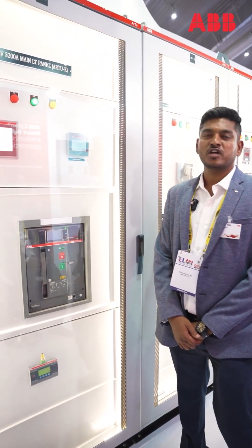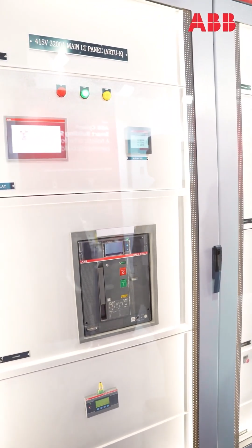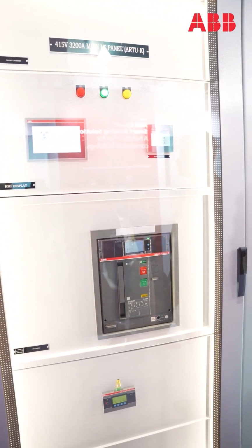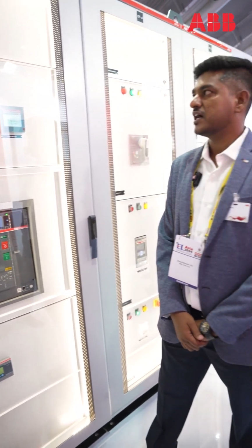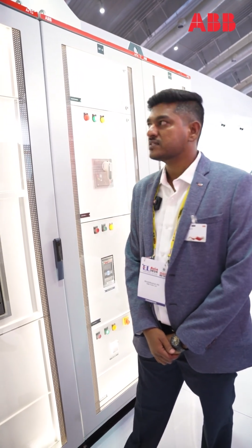This is an IEC 61439 type-tested panel, so we call it the ArTuK panel in ABB. Not only 614, we also tested our EC61641 as well as a seismic zone test on these panels. We have tested these panels in both aluminium as well as copper. Aluminium we have tested up to 5000 amps. In copper we have tested up to 6300 amps.